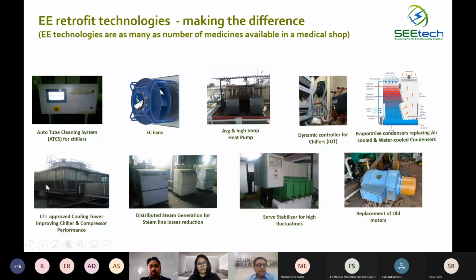Then on the second line is a cooling tower, a CTI approved cooling tower. Now what is a CTI approved cooling tower? CTI is the Cooling Tower Institute, and they have come up with a specific design. These cooling towers are costly, but if you make a smaller cooling tower, your energy consumption in the chiller goes up. In one of the examples, we will see what is costly: whether the equipment is costly or the energy cost consumed by this equipment is costly. We will see it there.